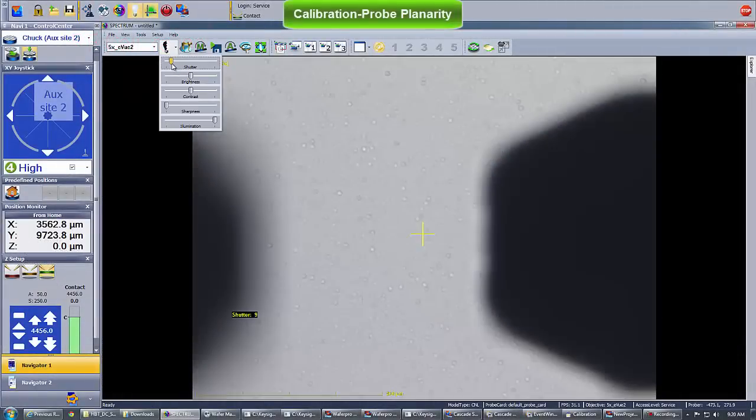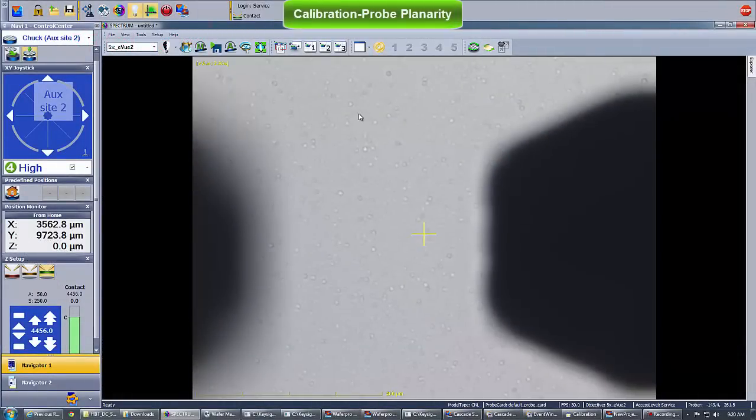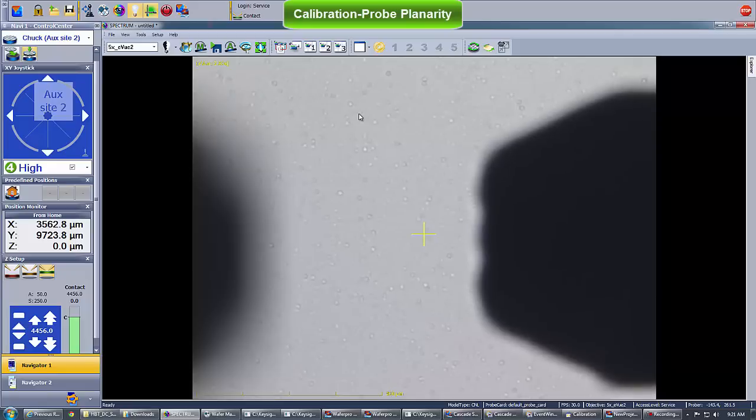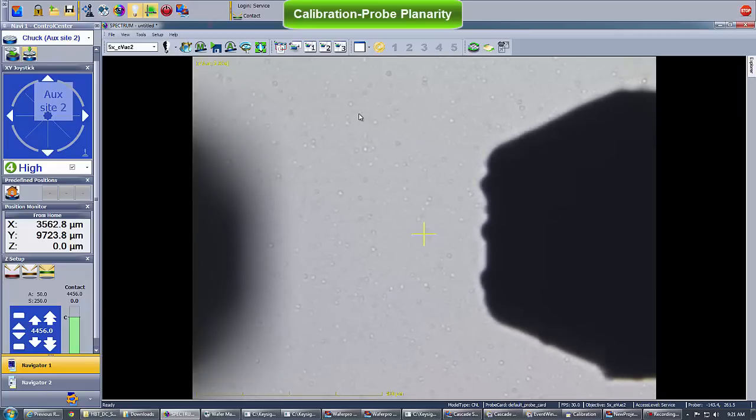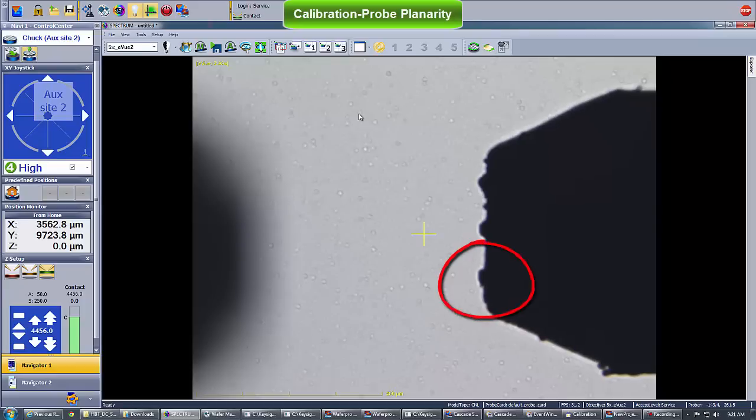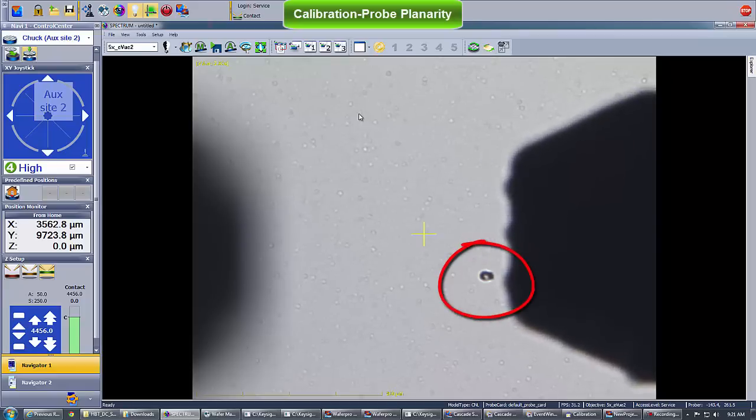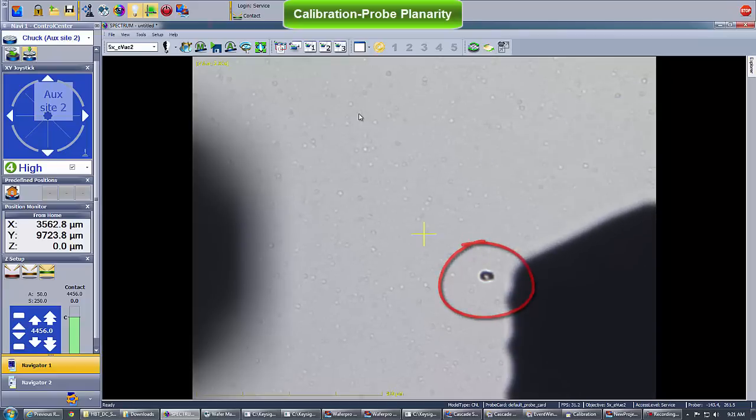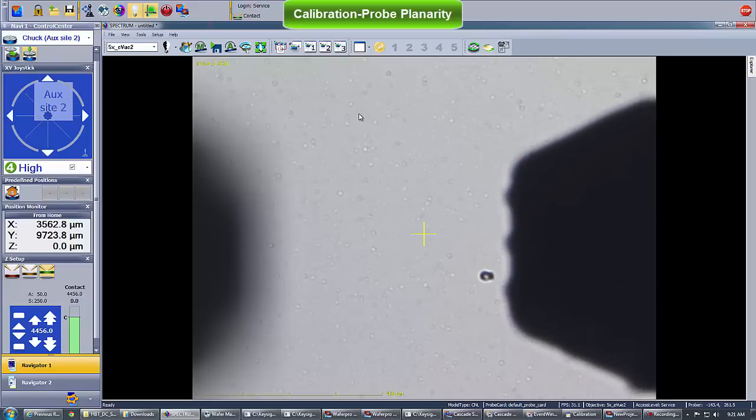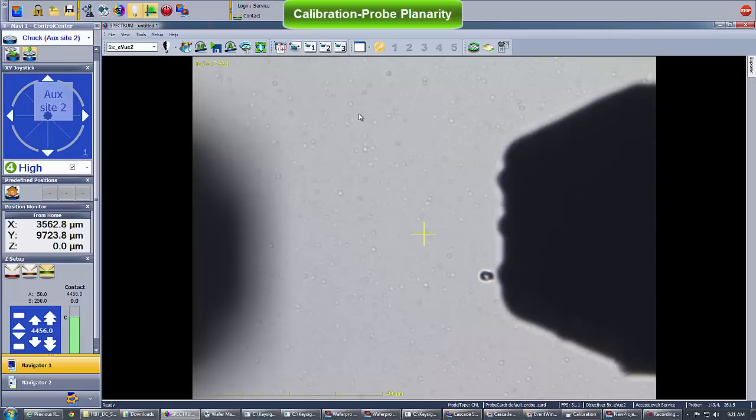Probe planarity ensures that all the probe tips touch the surface at the same time as contact is made. Incorrect planarity leads to inaccurate and unstable calibrations. Here's an example of non-planar contact where only the lower tip of the right ground signal ground probe touches the surface.